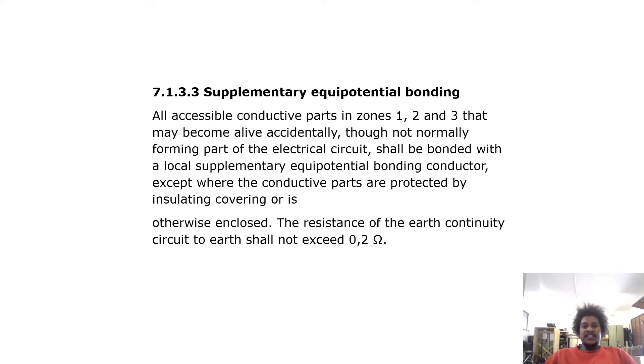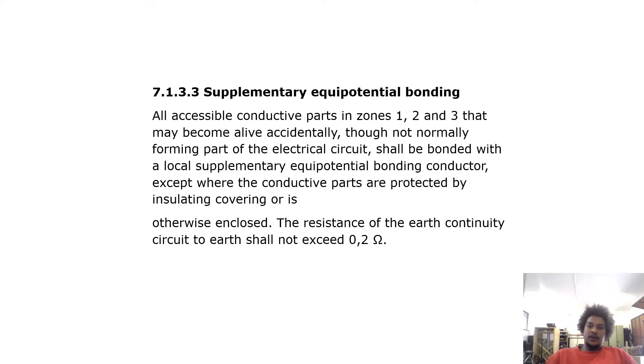All accessible conductive parts in zones 1, 2 and 3 that may become live accidentally — though not normally forming part of the electrical circuit — shall be bonded with a local supplementary equipotential bonding conductor, except where the conductive parts are protected by insulating covering or are otherwise enclosed. The resistance of the earth continuity circuit to earth shall not exceed 0.2 ohms.